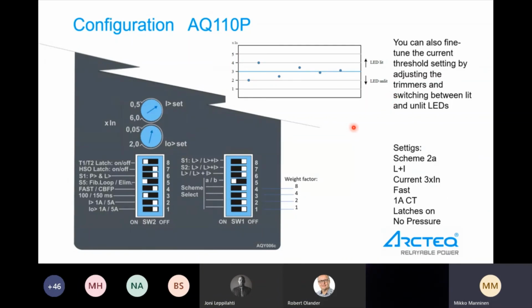With the Arcteq relays, it is not that critical because this has nothing to do with selectivity of any other protection relays. So our selectivity comes from the light and from the light detector. Latch is on, no pressure. So from these switches, we can select latch is on, high-speed output, latch is on. Latch on means that the relay will keep the trip outputs closed until we reset from the relay. Pressure and light, we can select this off because we only use light in this case.